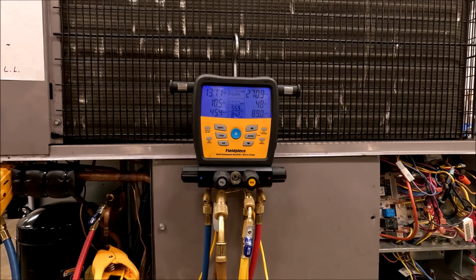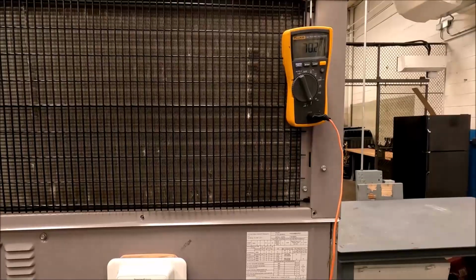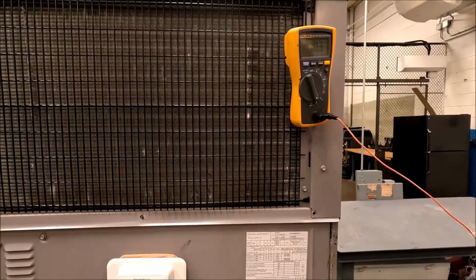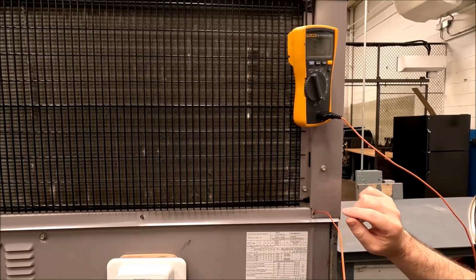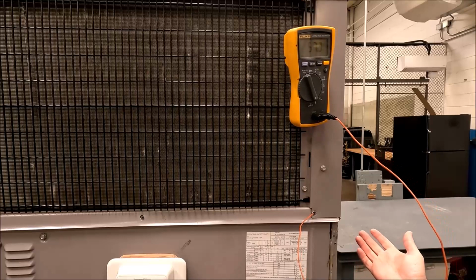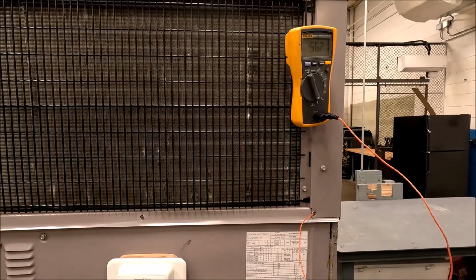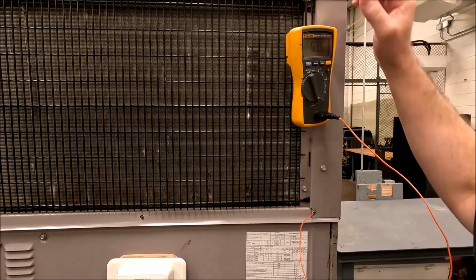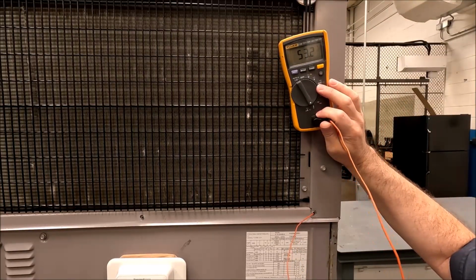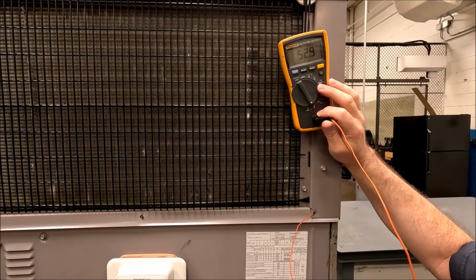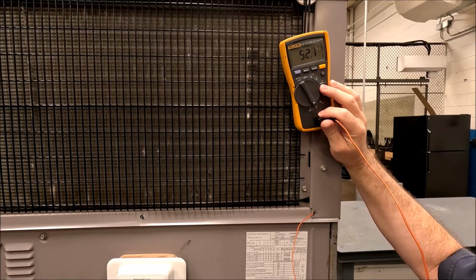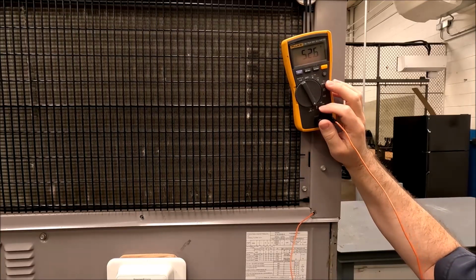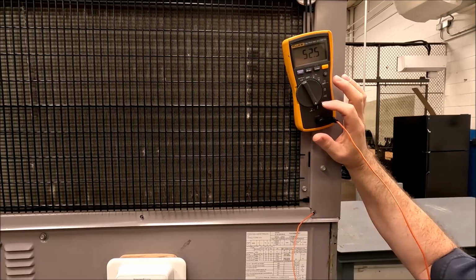Let's look over here. I've got a 71 degree return air temperature. Let's go see what our supply is. All right, real quick, like I said, already taking the screw out, save a little time. If I put that through there, it kind of feeds right in. This is a gas pack unit, so I've got a heat exchanger right there. You might feel a little resistance if you hit one of those cells. But as we're looking up top, I got 71 going in, and I'm already at 53, and it's dropping a little bit. So if it stops around the 51 or 50 degree mark, then we're in the money. I would leave the charge alone and let this unit ride.